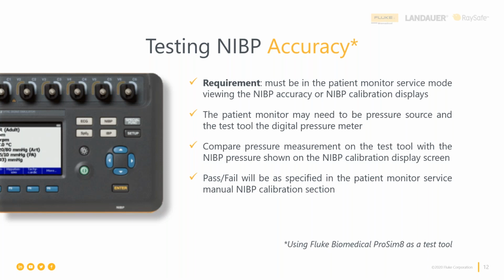All right, you with me? So the requirement here is that I must be able to seal the pressure relief valve, to close it. I have to be in the service mode usually in the NIBP calibration section to be able to do that. And once I'm able to do that, then I need to understand, in many cases, the patient monitor wants to be the pressurization control device. So in other words, we're not going to use our test instrument to do the pressurization of the system now. The patient monitor wants to do that, so we go ahead and let it. And now our measurement device, our test instrument, is going to be our transfer standard, having been and maintained in calibration.